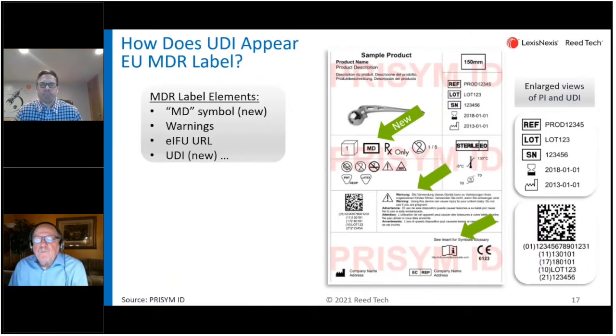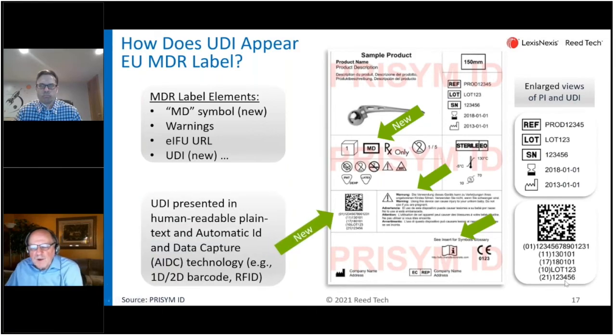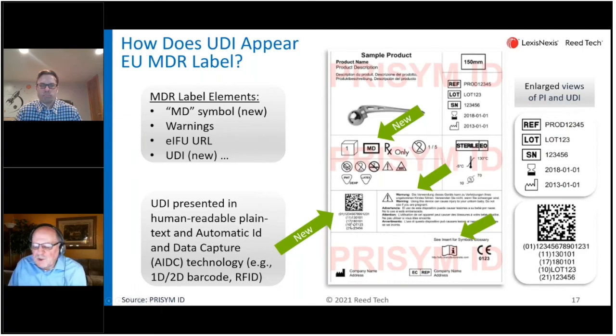One quick comment about labels: how does UDI actually appear on an MDR-compliant product label? You'll see a number of things there. Be aware there's an MD symbol for medical devices. For UDI presentation, this example has a 2D barcode followed by the device identifier and those additional production identifiers.